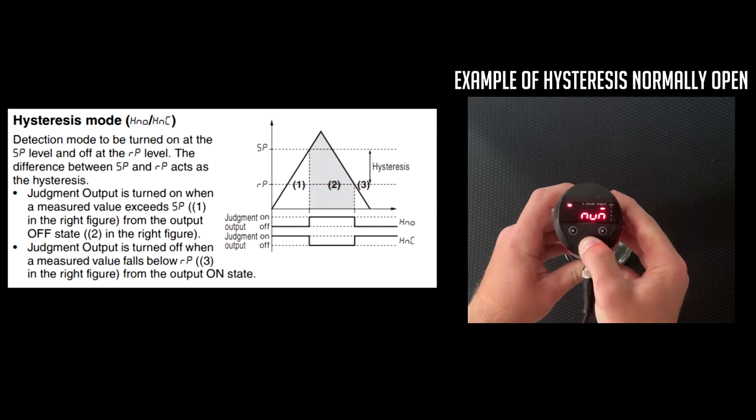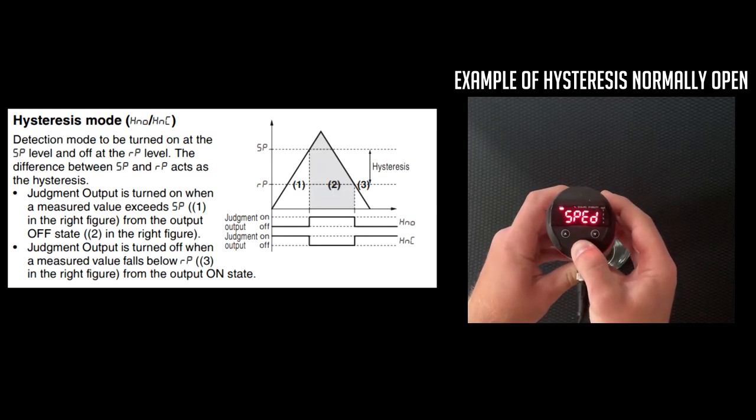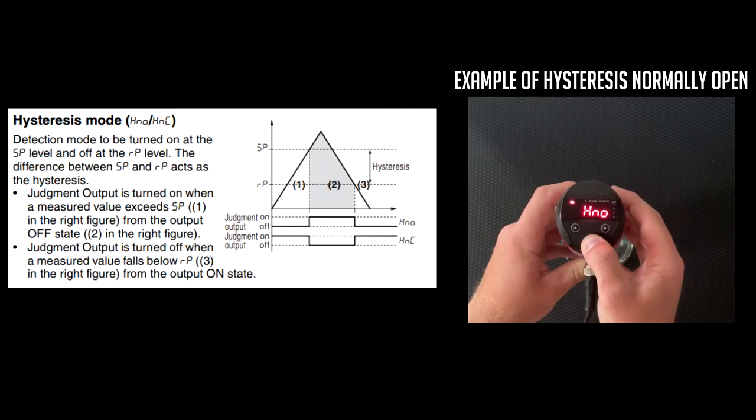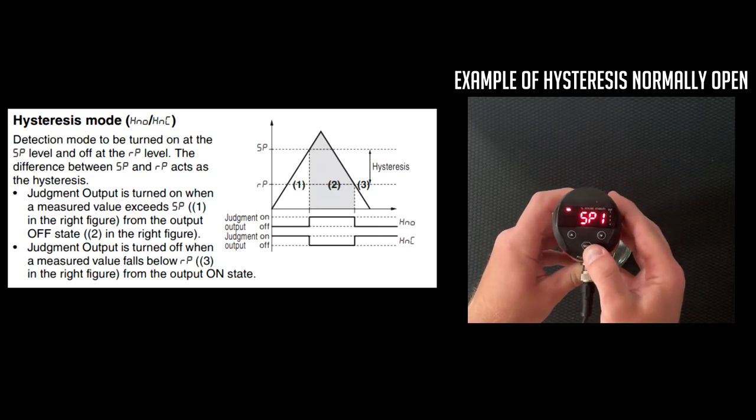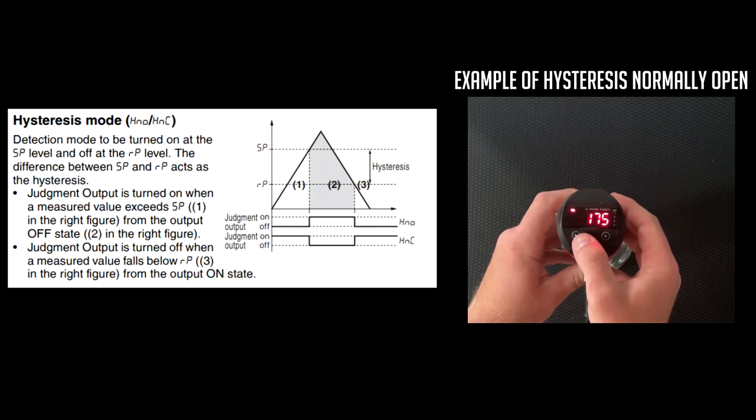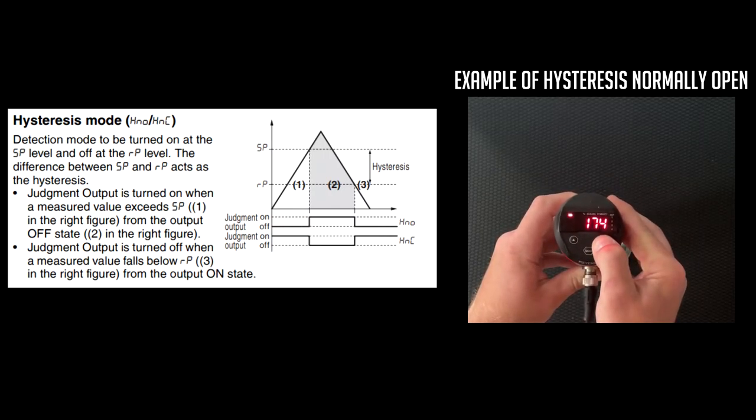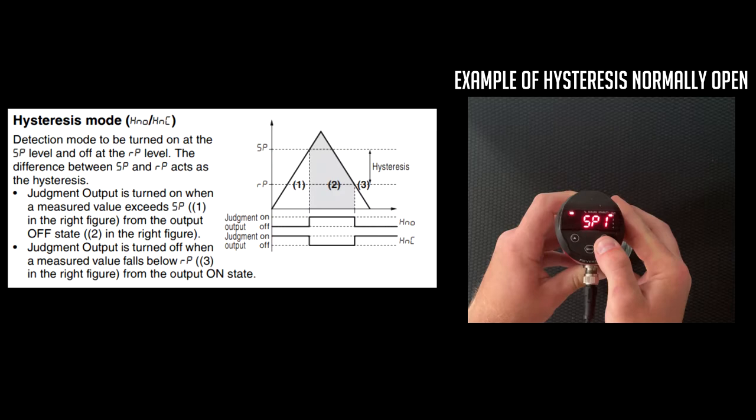To see which detection mode you're currently in, go through your basic settings, past your extended functions, until you see OU1, and that will tell you if you're an HNO or HNC. To then set your SP and your RP, you're going to go into the basic settings until you see SP1, set your level for SP1. Then go into your RP1 and set your level for your RP1.